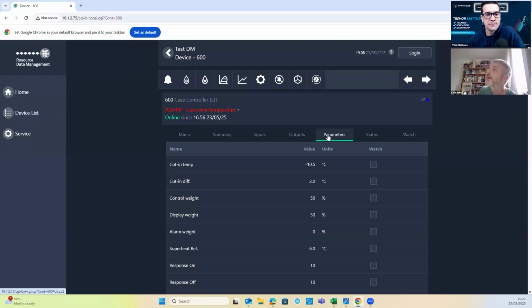And what you find with RDM is that the majority of the time, the default parameters will start the fixture up. But they are almost certainly not going to be what you want. Now, if you've selected a type file, your types 1 to 6, that's LT, it'll default to -20 as your set point. If you've selected HT, then it'll default to 0. On a 50% weighting as they are there. So that's taking its control value to be 50% of the air on, 50% of the air off.